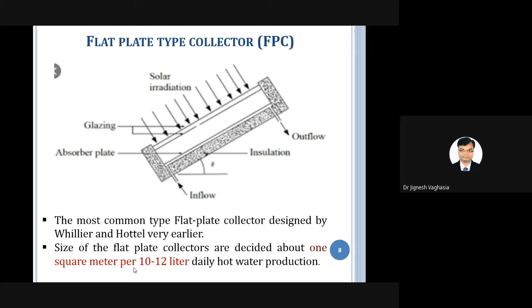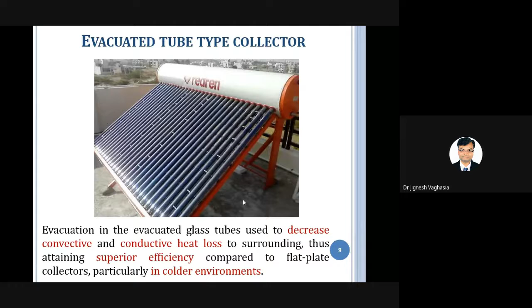Other is the evacuated tube type of collector. Here, a simple absorber tube and an evacuated glass tube are used. The purpose of the evacuated glass tube is to decrease the convective and conductive heat loss. By means of evacuation, it reduces the convective loss, and there is no metal part, almost no physical contact, so conductive loss is also reduced. That's why it has a superior efficiency compared to a flat plate type of collector.